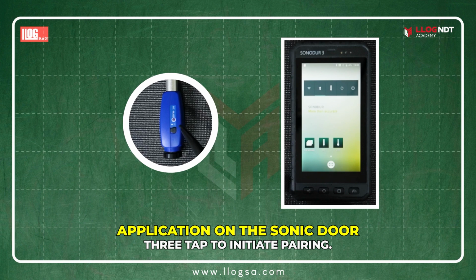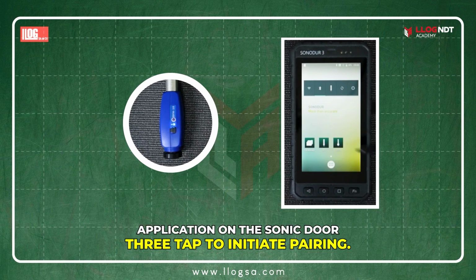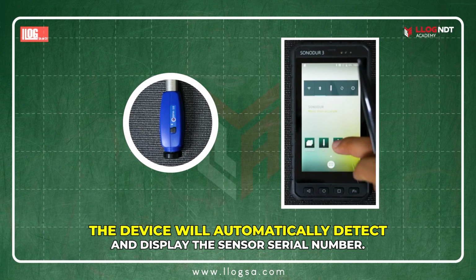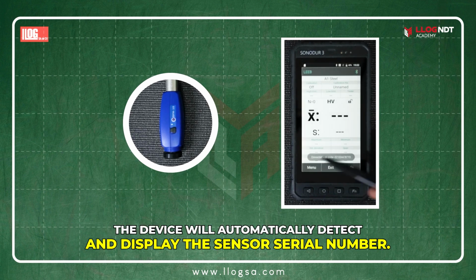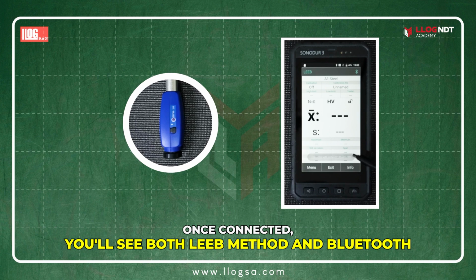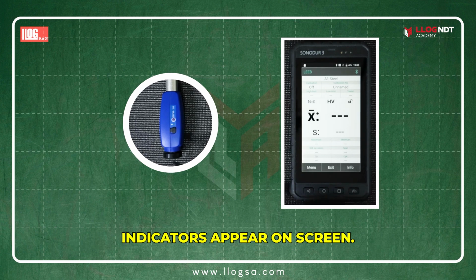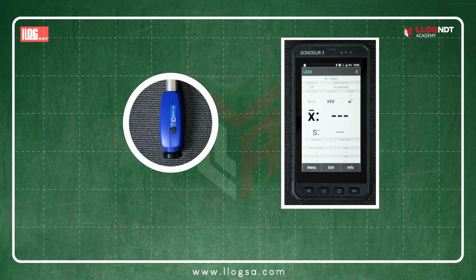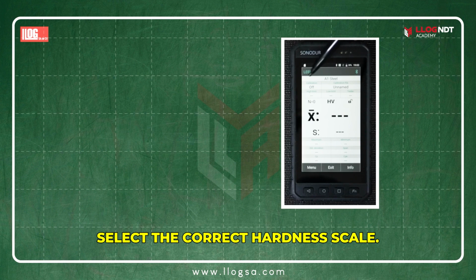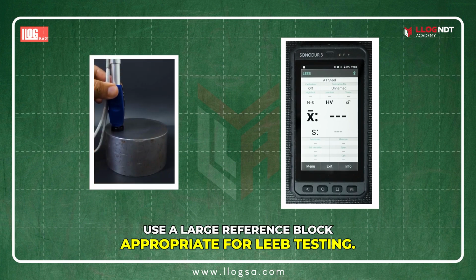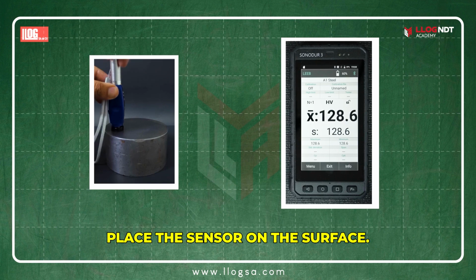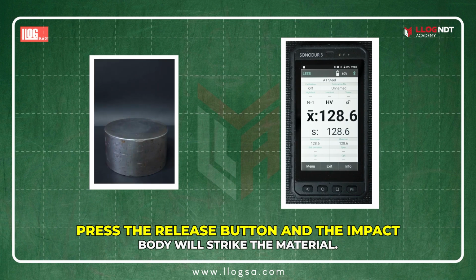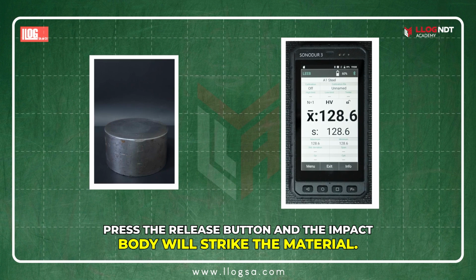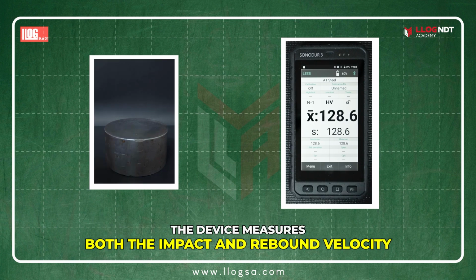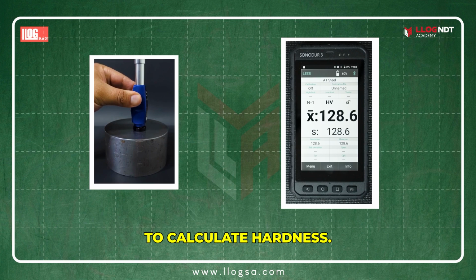Then, launch the Leeb application on the Sonodur 3. Tap to initiate pairing. The device will automatically detect and display the sensor's serial number. Once connected, you'll see both Leeb method and Bluetooth indicators appear on screen. For standardization, select the correct hardness scale. Use a large reference block appropriate for Leeb testing. Place the sensor on the surface, press the release button, and the impact body will strike the material. The device measures both the impact and rebound velocity to calculate hardness.